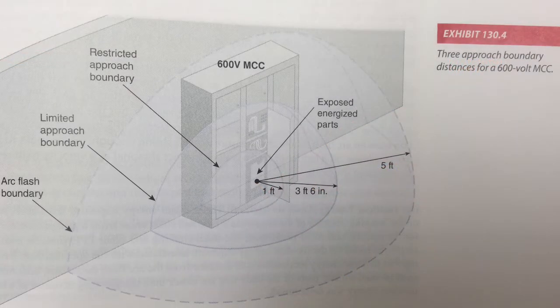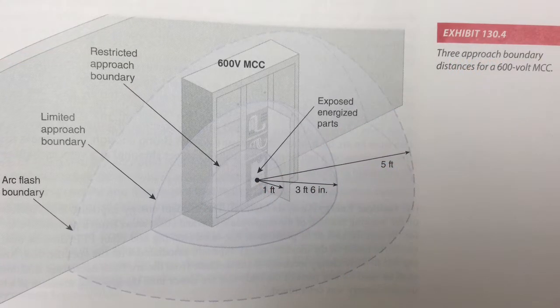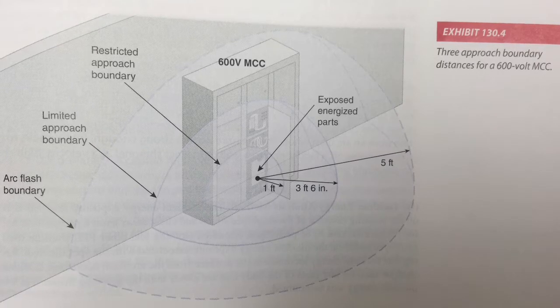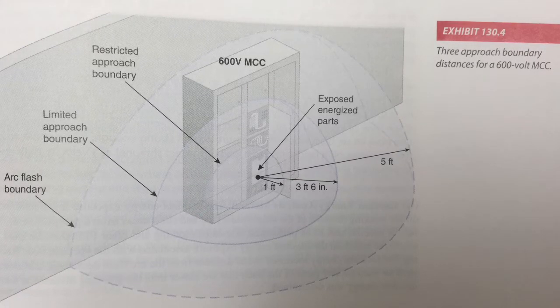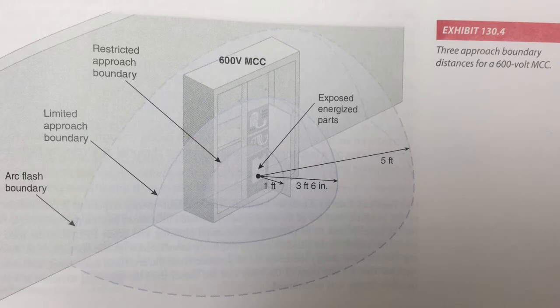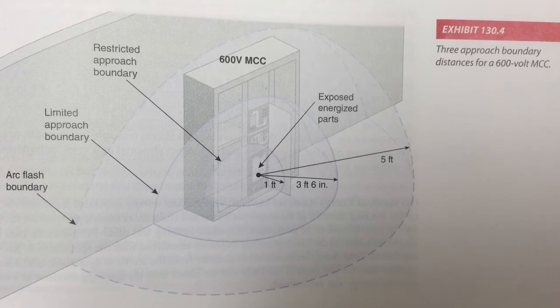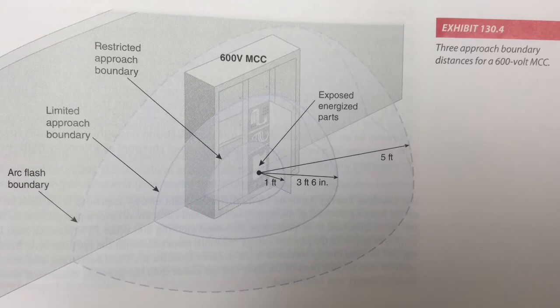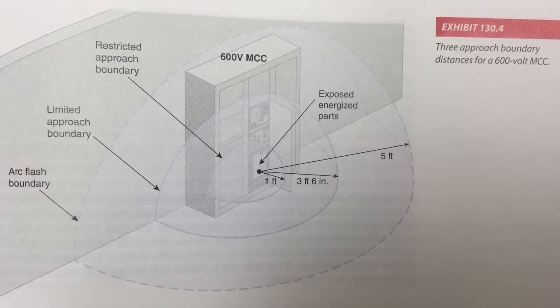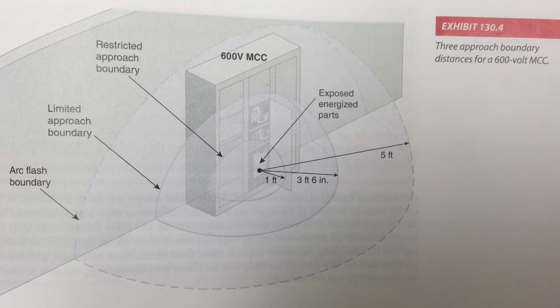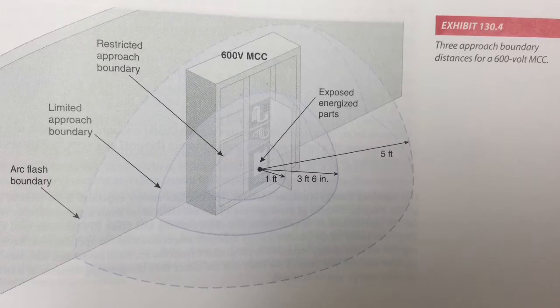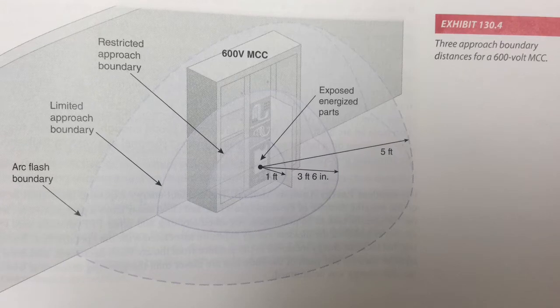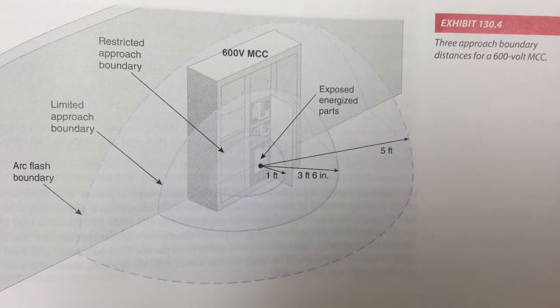This picture shows the approach boundary distances for a 600-volt MCC. The arc flash boundary is the distance at which the incident energy equals 1.2 cal, which is expected to limit your injury to one that is recoverable and non-permanent. This does not necessarily mean that an injury at this energy level will not result in hospitalization. The arc flash boundary is 5 feet, the limited approach boundary is 3 feet 6 inches, and the restricted approach boundary is 1 foot.